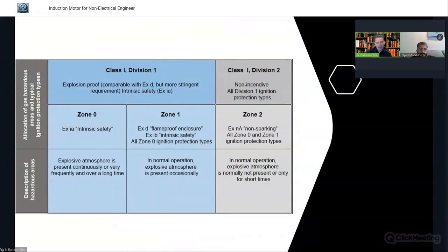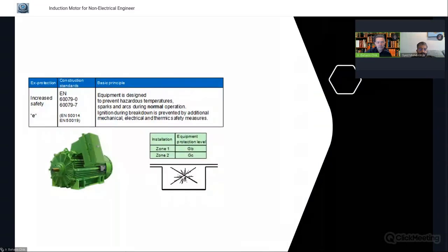A little bit about the zones. Zone 0, where we need to use IS circuits or equipment. And zone 1, we need to use EXD, and as an option, we can use EXP as well. Then for zone 2, we can use EXNA. This is the motor for increased safety, EXE, which is suitable for zone 1 and zone 2. But these are very expensive motors. Normally, we don't use EXE motors.